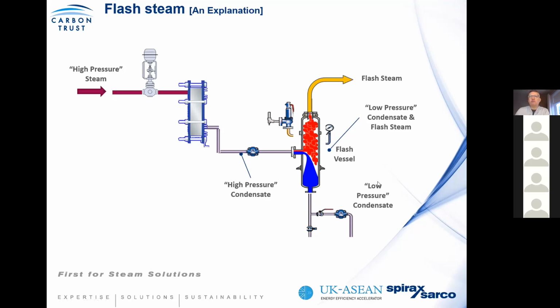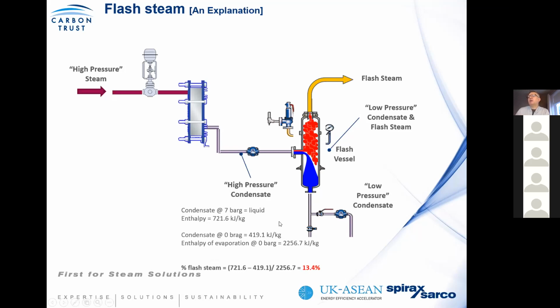If this was your condensate recovery unit, what you're seeing on the vent from a condensate recovery unit is a lot of flash steam. And this is unavoidable if you're using high temperature processes. Now, let's consider, as a case example, that this was 7 bar. According to the steam tables, water or condensate at 7 bar has an enthalpy of about 721 kilojoules. However, please remember that condensate at 0 bar can only hold 419 kilojoules. So the condensate will want to release the difference between the 721 minus the 419.